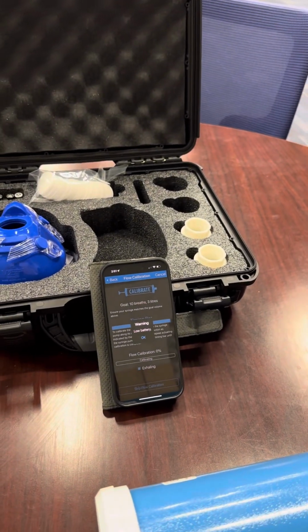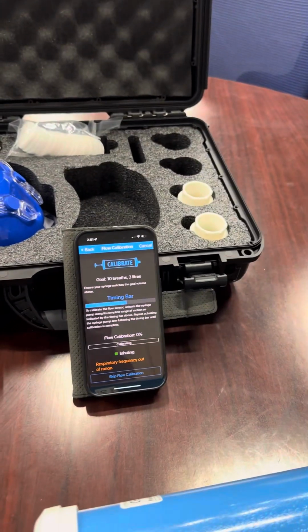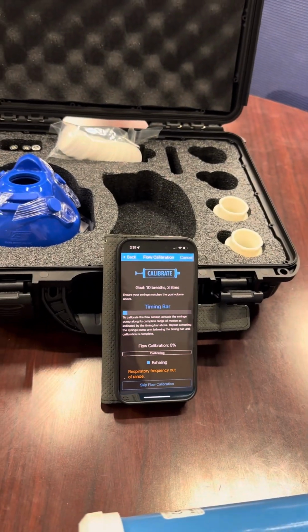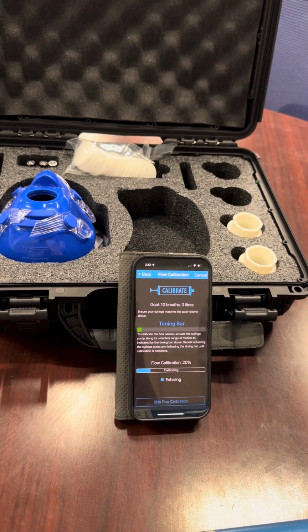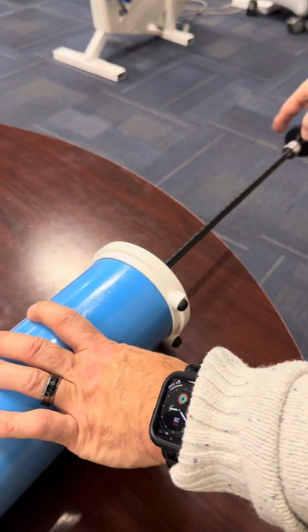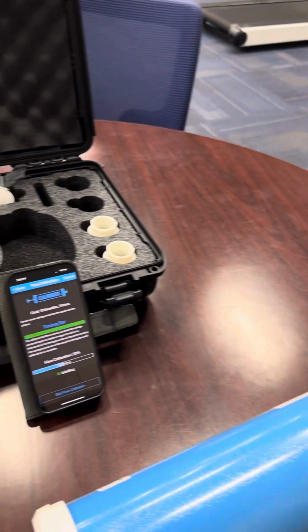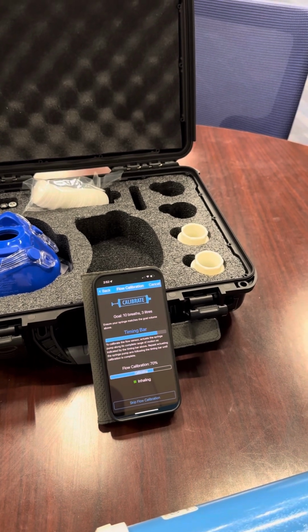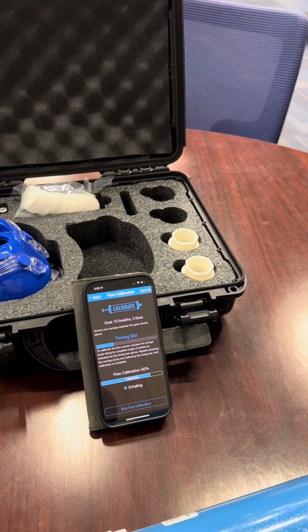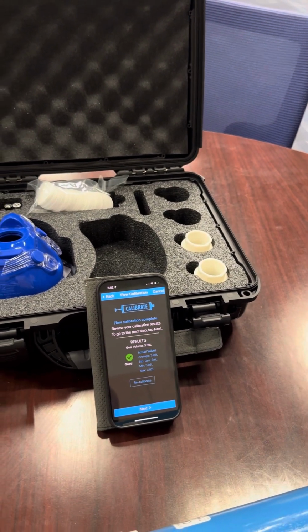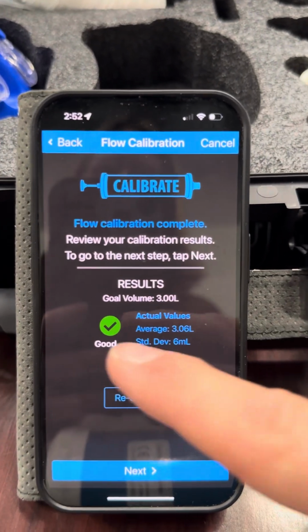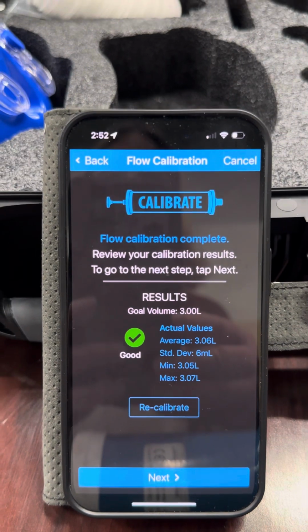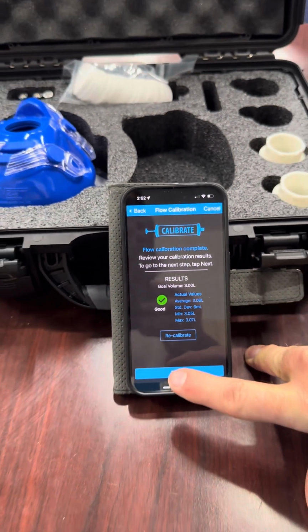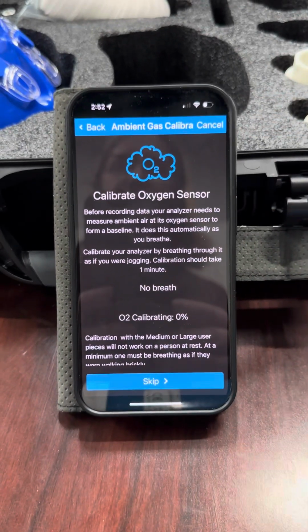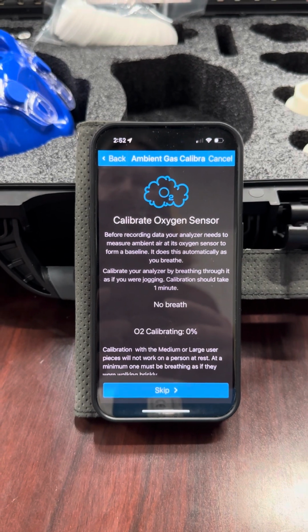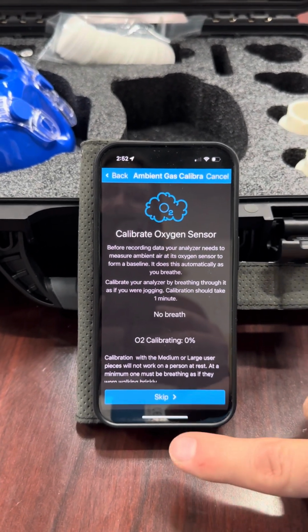And then you can look, and as the flow calibration is the bottom bar, and as it starts to work its way all the way across, that means it's calibrating. So this is what it looks like when it's fully calibrated. It says good, and then you move to the next part of the test, or you can start the testing. If we hit next, this actually takes us into having the person set up with the VO2 on their face. Okay, so I'll shoot that in the next video. Okay, that's enough.